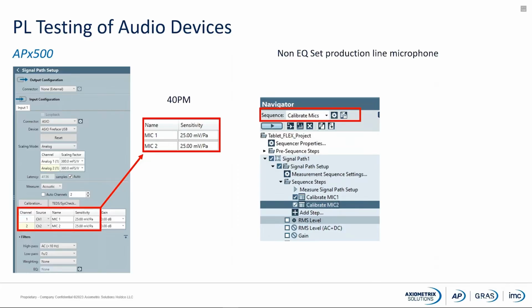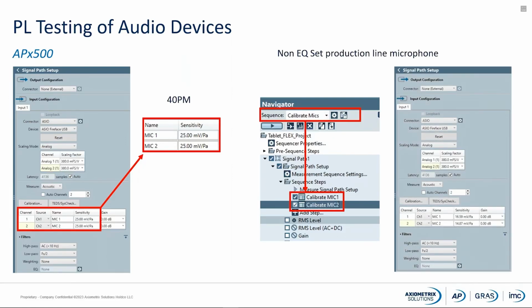So if you use the 40 PM, there's really no need for a sequence at all to calibrate the mics. And typically in a production environment, this would be carried out by a technician level employee. So again, using the 40 PM, you can just leave the production line with a standard operator to run the projects. And there's an image here with the individual sensitivity of the two mics shown on the right hand side. Whereas when we use the 40 PM, we've got the same sensitivity and no calibration required.